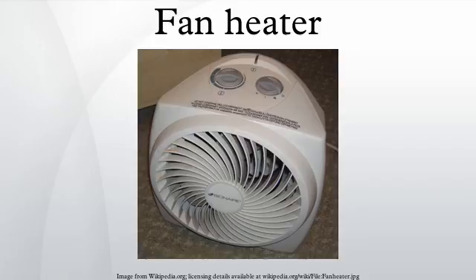Industrial model. Industrial fan heaters use finned heating elements in front of the fan to provide a larger airflow and higher kilowatt rating than the smaller residential fan heaters. Industrial fan heaters can be used in warehouses, shipping containers, clean rooms, shops and other general-purpose heating applications. They can also be used as dryers or dehumidifiers with modified attachments or mountings. Portable industrial fan heaters tend to range from around 2 kilowatts up to about 21 kilowatts with either axial or centrifugal fans and various staged controls and over-temperature safety cutouts.